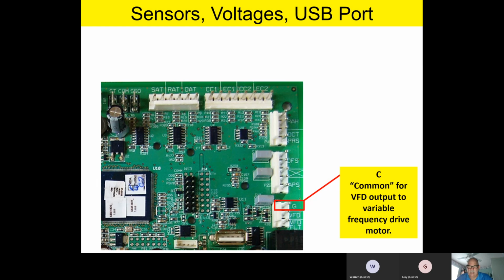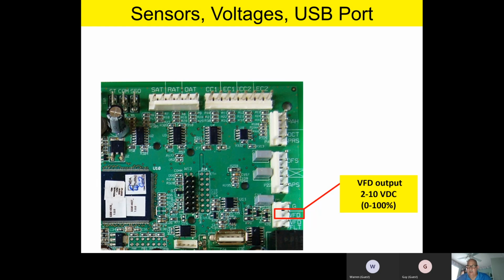This is an onboard common for variable frequency drive output to the variable frequency drive motor. So this is a VFD output. It's a common for the VFD output. Now watch this. If you've got a variable frequency drive blower, this VFD output from the board will be a 2 to 10 volt DC output to drive that variable frequency drive 0 to 100% airflow capacity.